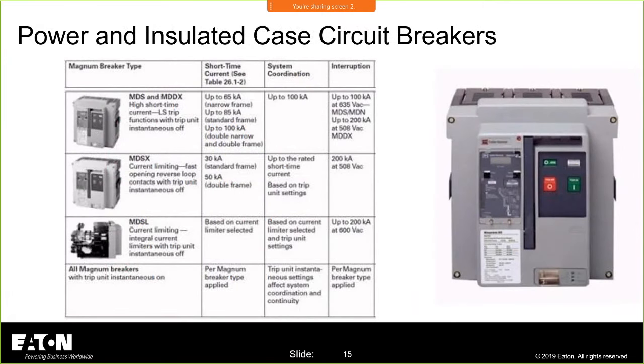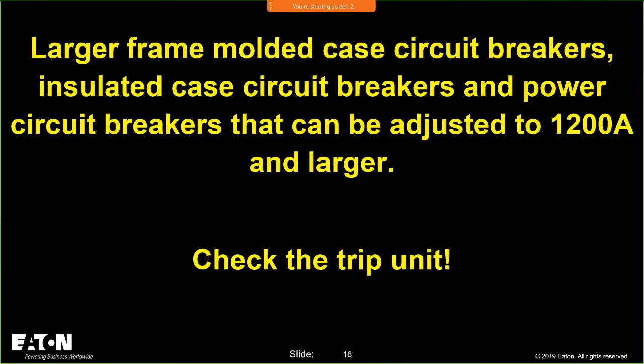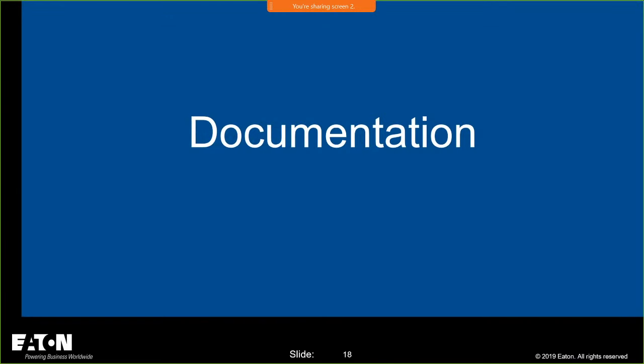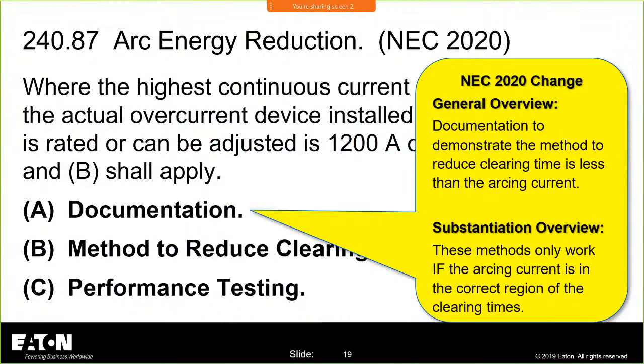All right, so this is our insulated case circuit breakers. These devices are all pretty much going to have an arc reduction technology as well. Larger frame molded case circuit breakers, insulated case circuit breakers, and power circuit breakers that can be adjusted to 1200 amps and larger. Check the trip unit, check the capabilities of the devices that you're looking at. That's going to be critical and very important to determine whether or not you are into a technology requirement.